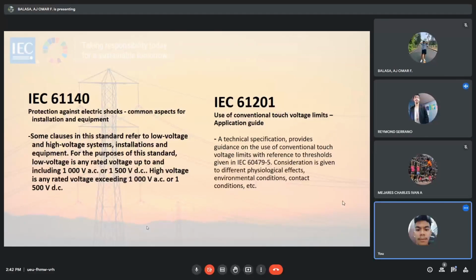So next is IEC 61201, use of conventional touch voltage limits, application guide. This technical specification provides guidance on the use of conventional touch voltage limits, with references to thresholds given in IEC 60479 Part 5.